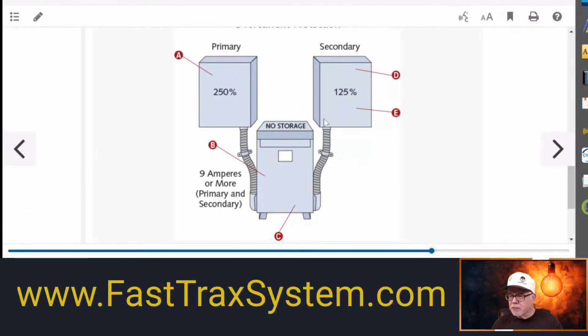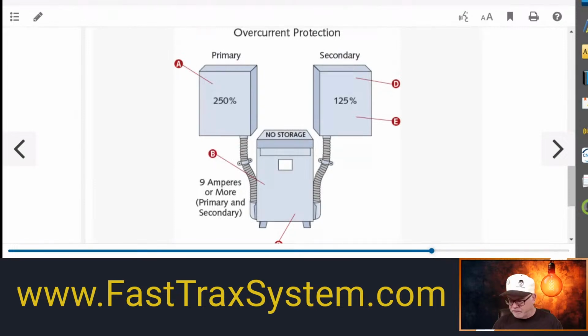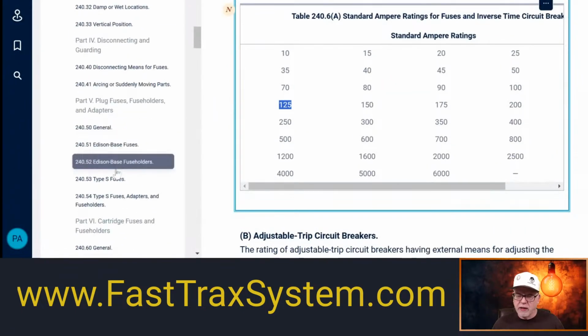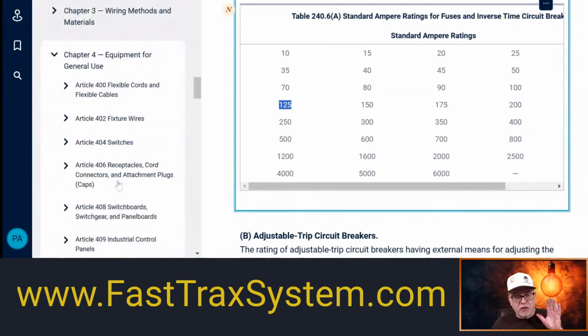All right. Cool. All right, so let's talk protection real quick here. If I look at the National Electrical Code, and we'll go there real quick, let's look at transformer protection. This is probably what you could deal with most of the time, because in a majority of the situations that I see, whether it's TikTok, Instagram, wherever it is, the majority of the people are taking a transformer and they're hitting a panel that's right next to it, or usually within 10 feet or in close proximity. Okay, now, we're not going to be sizing secondary conductors and all that kind of stuff. We're going to do that for another video that gets you hyped up.